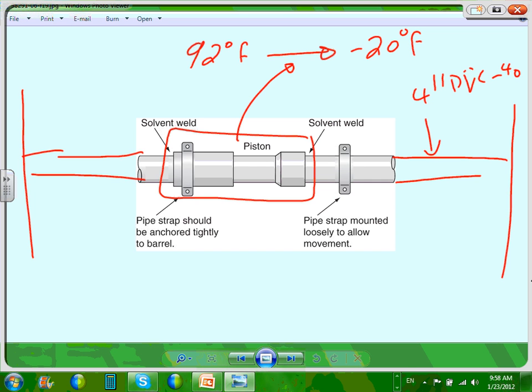So what happens? If you look, this conduit is allowed to move loose with this piston. So in the winter, what happens to the conduit? It shrinks, so it will come this way, and it's still connected. In the summer, it's going to expand and go that way. And if you size it right and install it right, the conductors will never be exposed. Any questions, guys, about the expansion fittings?